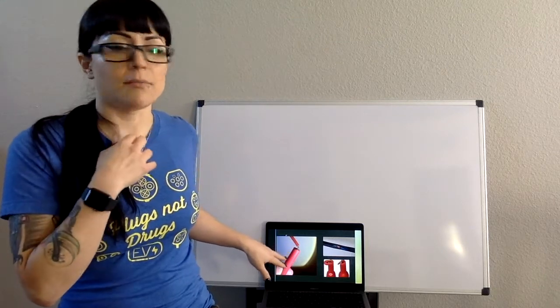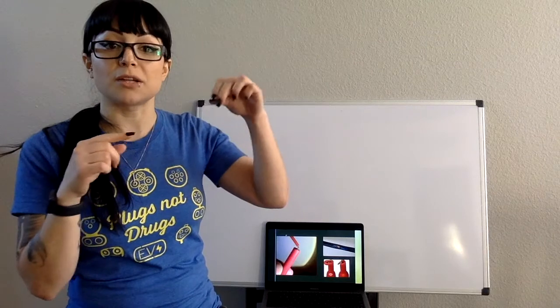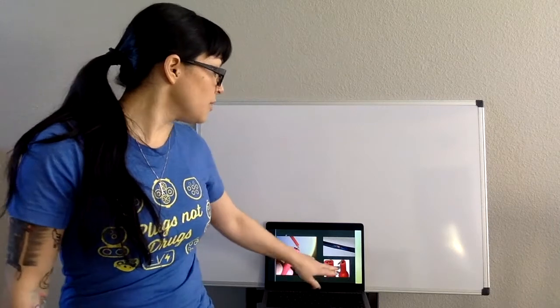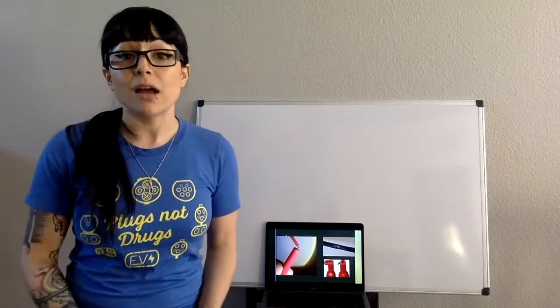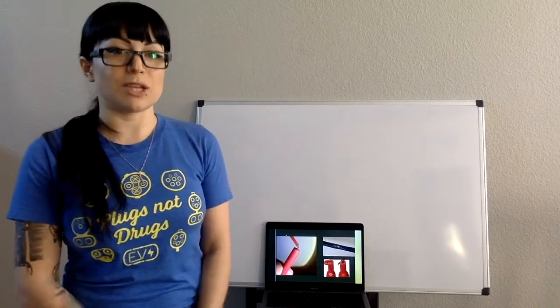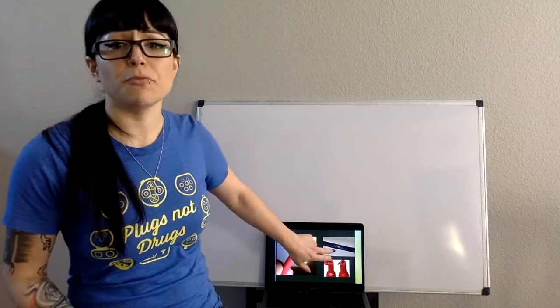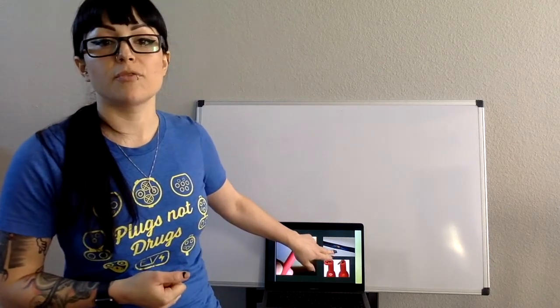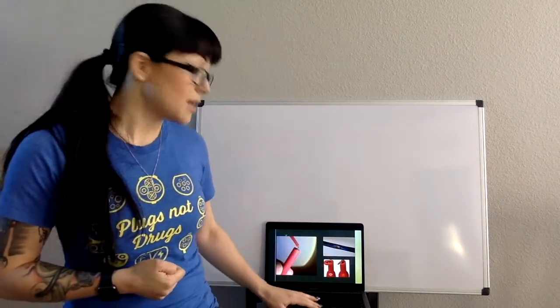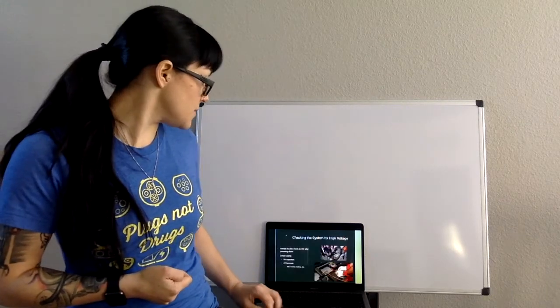So there are a couple of good visuals in the pictures that I gave you in your slides. We've got a common problem where the lead head will start to disconnect from the meter lead wire. We've got hooks that get bent and melted, and you're going to need to test all of the equipment you're using. So if you're using alligator clips, or any of the test hooks, any of that stuff, you need to make sure that you're testing it before you actually go to perform the test. There's also a really good picture of a melted or chafed wire for the lead as well. So that's a common problem and easily overlooked.